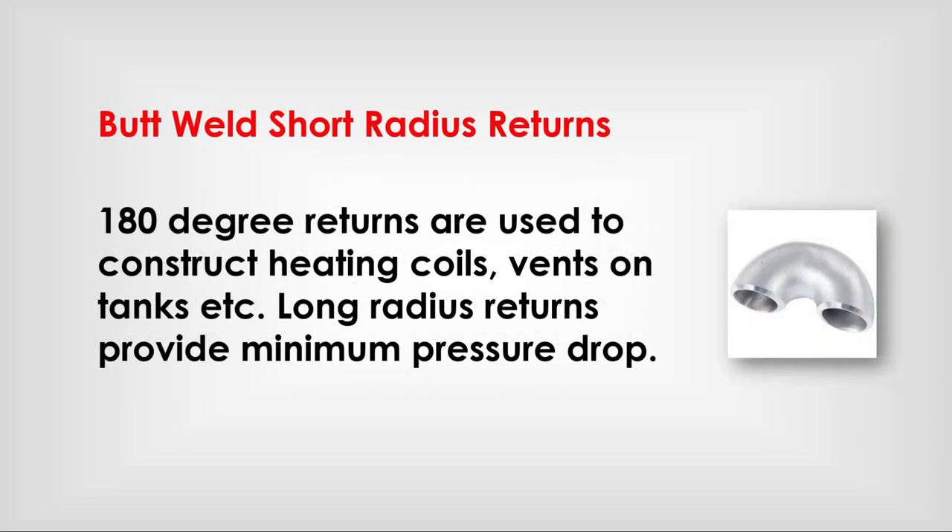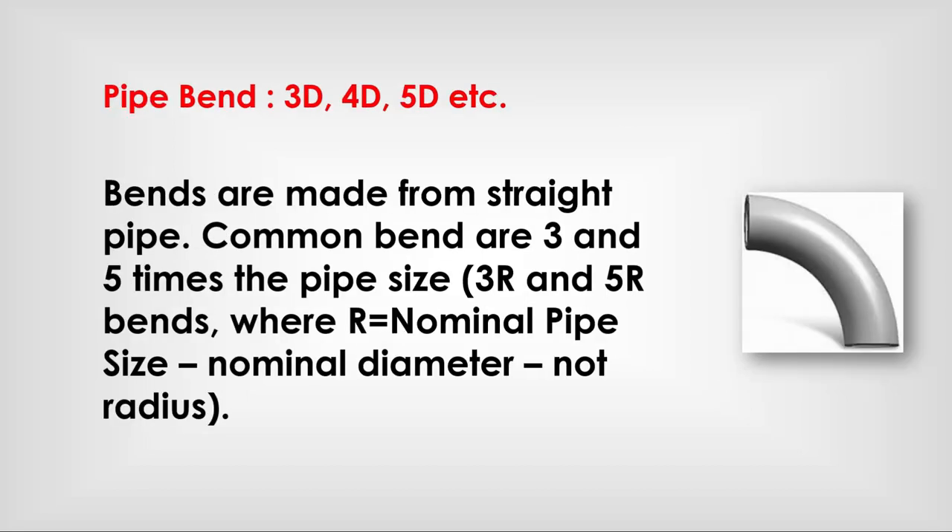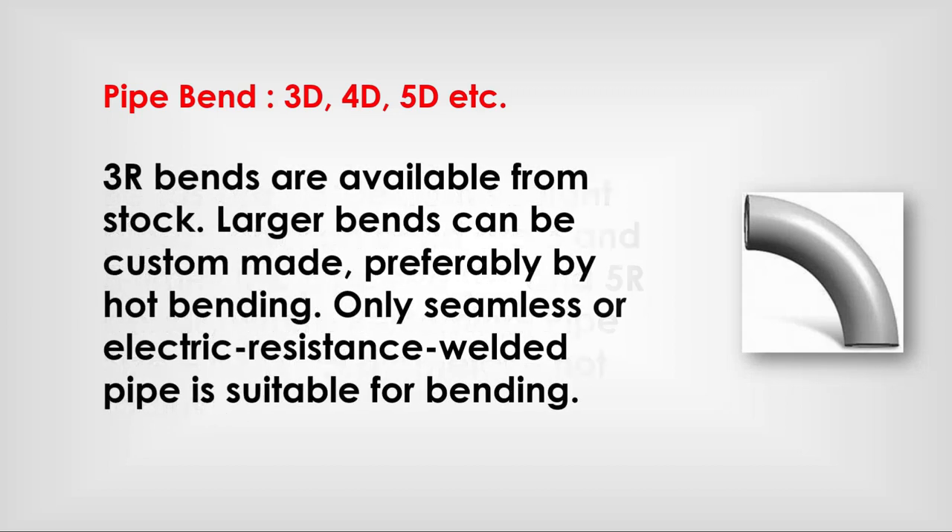Butt weld short radius 180-degree return: used to construct heating coils vents on tanks, etc. Long radius returns provide minimum pressure drop. Pipe bends — 3D, 4D, 5D, etc. — are made from straight pipe. Common bends are 3 and 5 times the pipe size, where 3D or 5D refers to nominal pipe diameter, not radius. 3R bends are available from stock; larger bends can be custom made, preferably by hot bending. Only seamless or electric resistance welded pipe is suitable for bending.